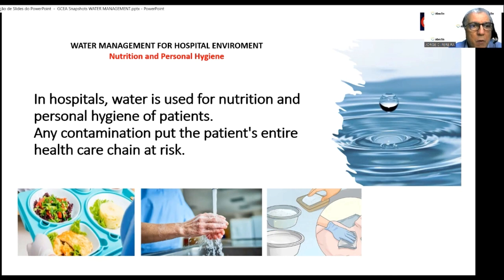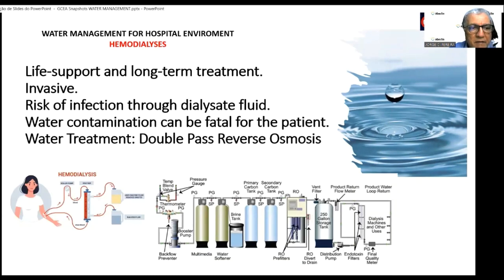Each one requires a specific post-treatment. For example, hemodialysis requires double pass reverse osmosis. Hemodialysis is a life support, long-term, and invasive treatment. Water contamination can be fatal for the patient due to the risk of infection through dialysate fluid that has water as one component. That is why water treatment for hemodialysis requires double pass reverse osmosis.